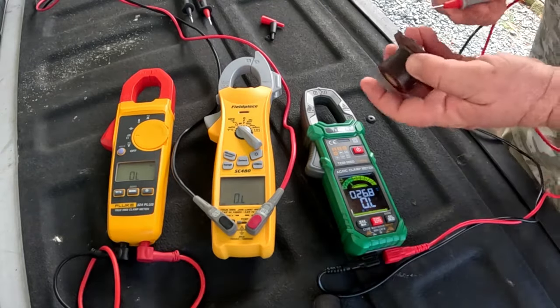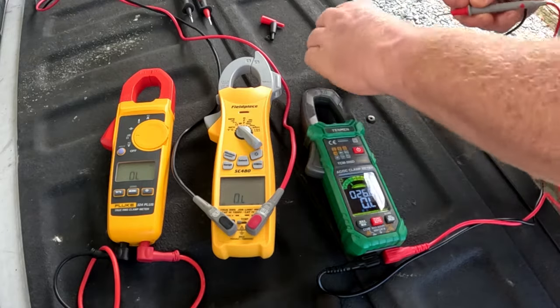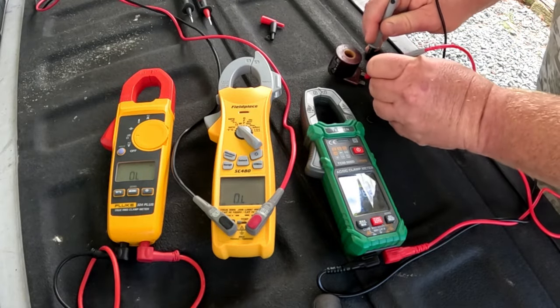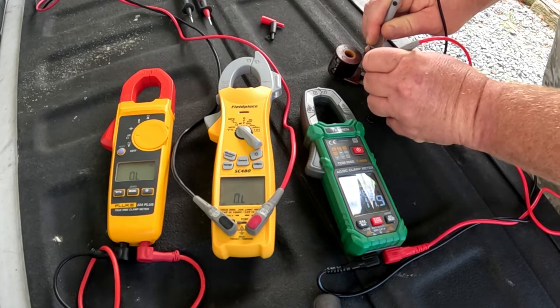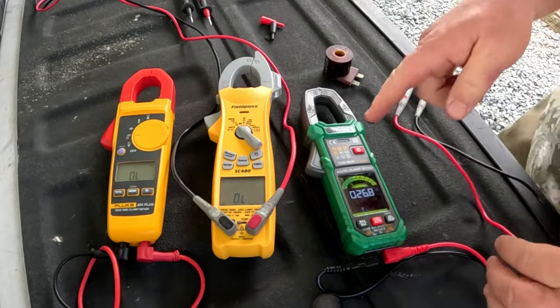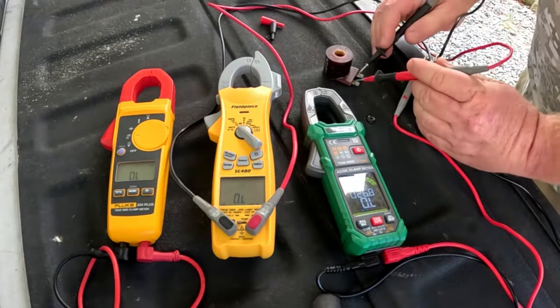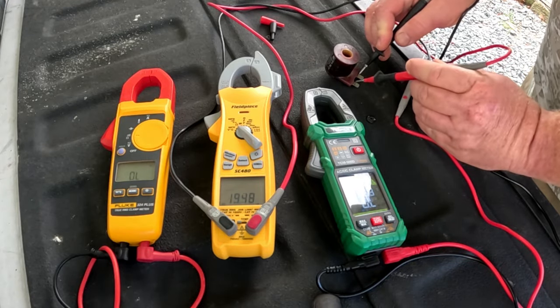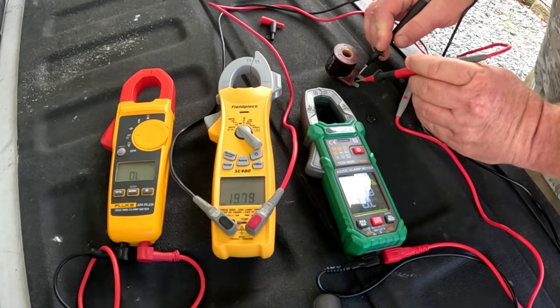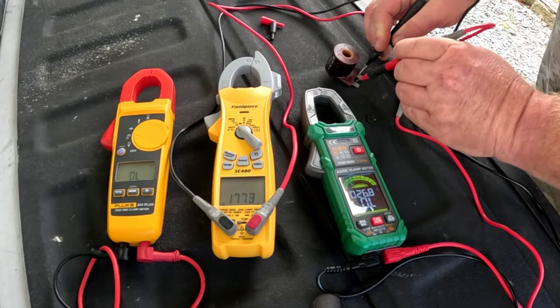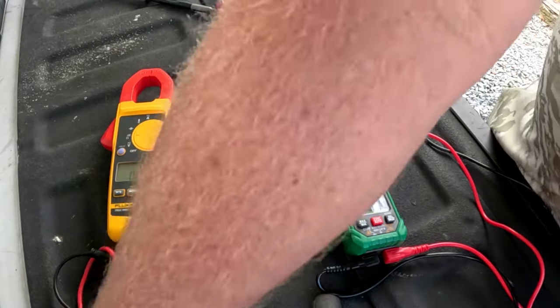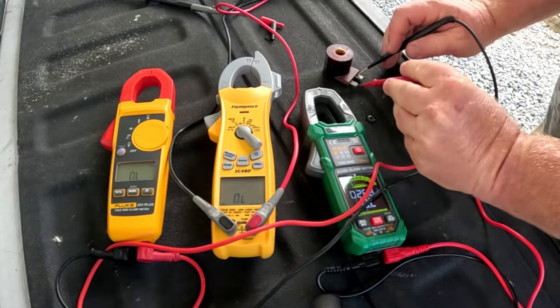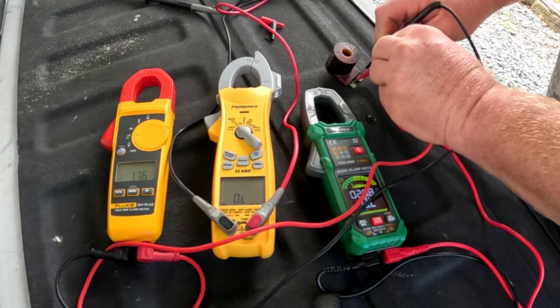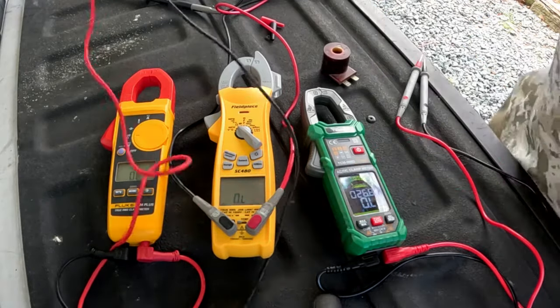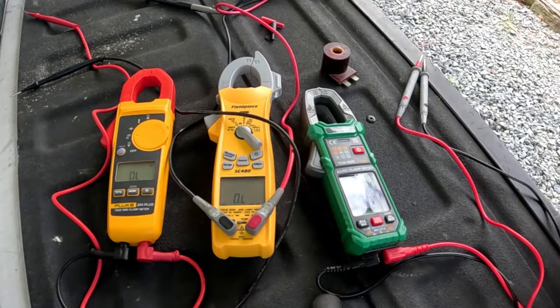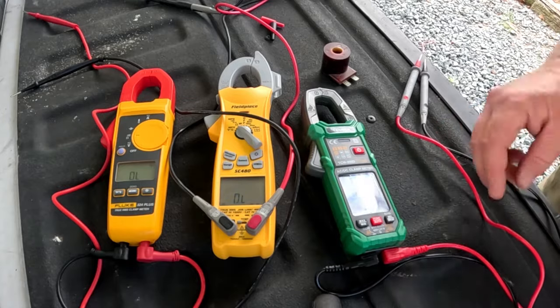Let's check a solenoid for a reversing valve. We'll start with this one first. 17.8 with the TESMEN. And we are at 17.7 with the FieldPiece. And 17.6 with the Fluke. So they're almost all reading exactly the same. This one just takes a couple of extra seconds before it registers.